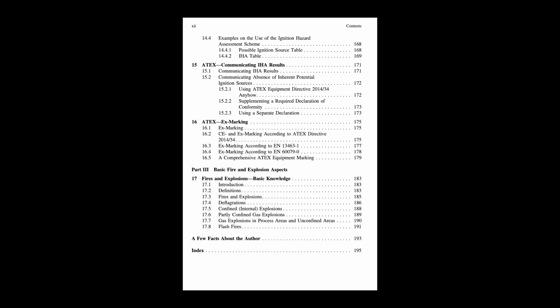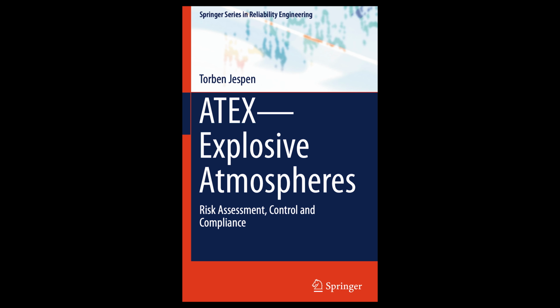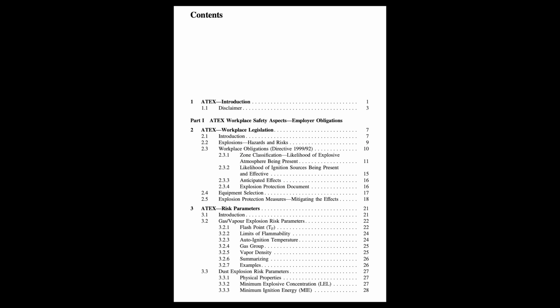Flame arresters, what are they? They're like special meshes or filters. They let normal process gas flow through, but they quench a flame front trying to pass. Other methods include rotary valves, which act as a physical barrier for dusts, or even just ensuring you have a sufficient choke of material in a screw conveyor to stop flame passage. Okay, so stopping the explosion from traveling, venting, containment, suppression, isolation. 4 key ways to mitigate. These sound absolutely vital if an explosion does kick off.